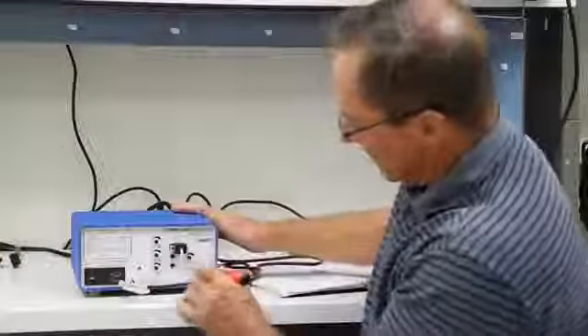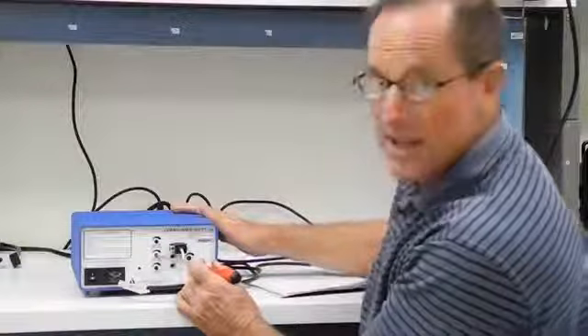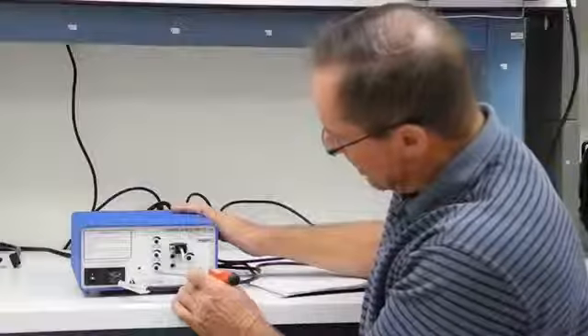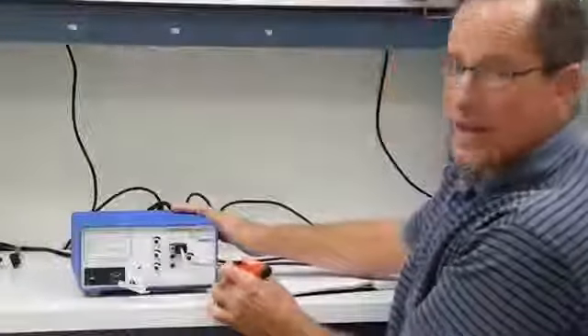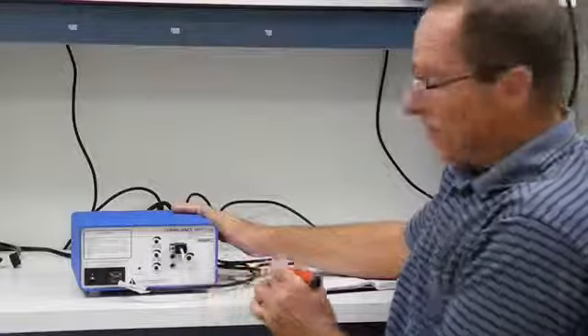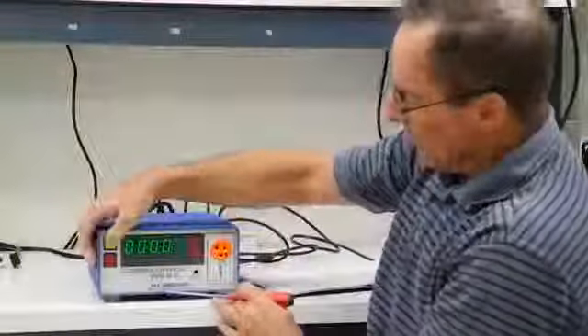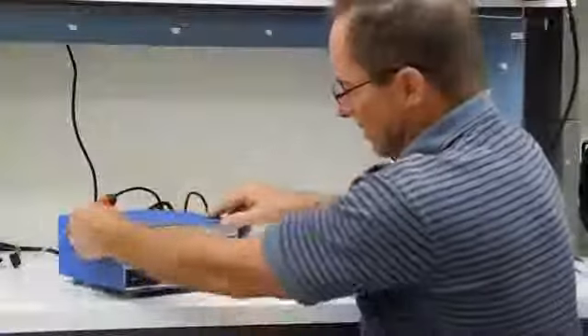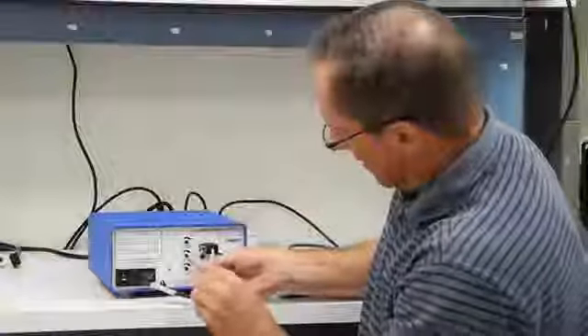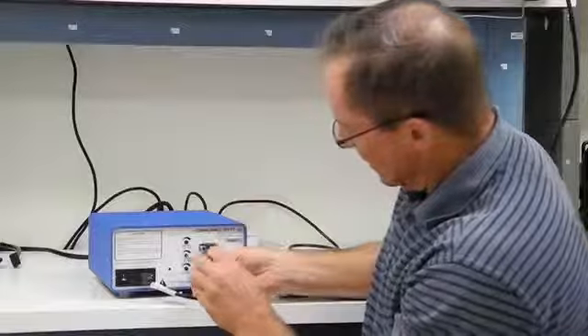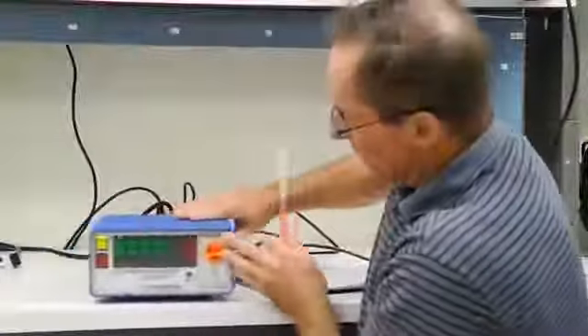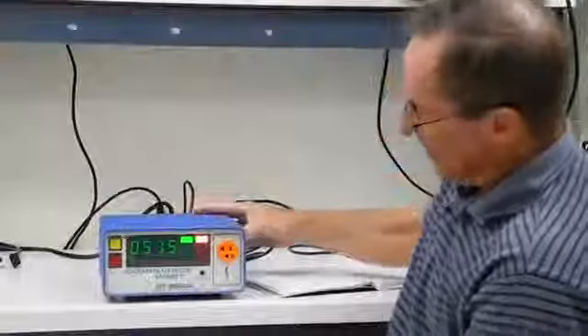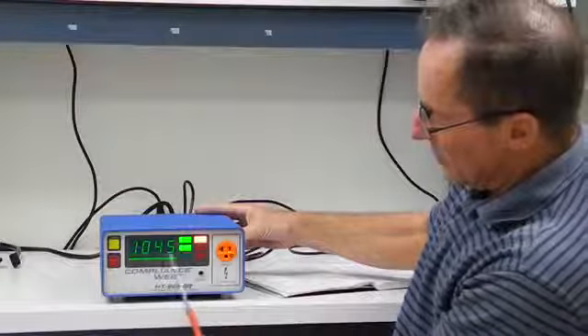You can see this one here, the middle one, is for test time. The bottom one is for leakage current, and over here is the voltage adjust. The way to do it is to start with the voltage adjust. What you do is you set the timer very high so that the tester will continue to test for a while. And then push the test button, and you'll see the voltage show up on the front panel.